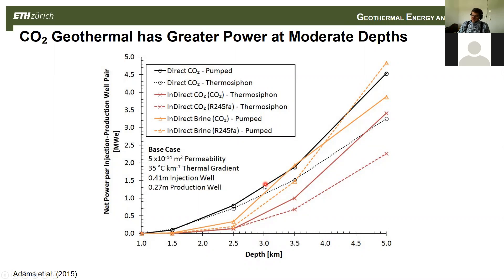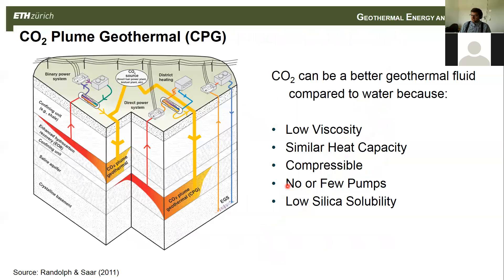There are two flavors of CPG plants. The solid line is a pumped CPG plant and the dashed line is a thermosyphon plant — basically without pumps. These CO2 plants generate their own circulation rate; the fluid will circulate without pumping at all, and that's called the thermosyphon-generated flow rate. If you want to pump, you can usually get additional power — as you can see, the pumped line is greater than the thermosyphon line. You can get more power out, but you don't have to. Today we're going to focus on this thermosyphon system, this naturally convecting CO2 system.